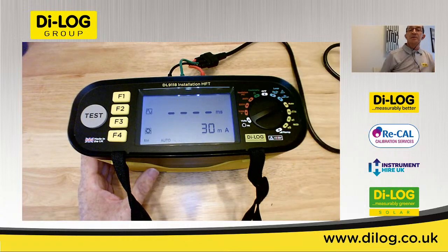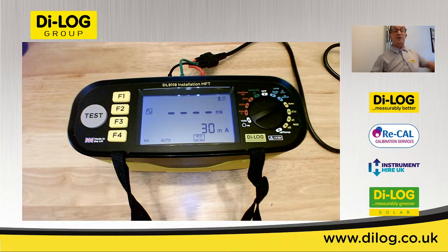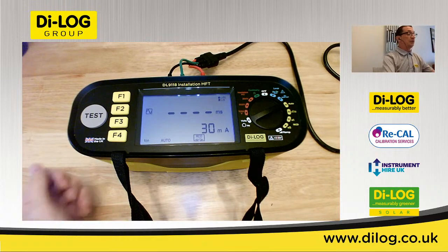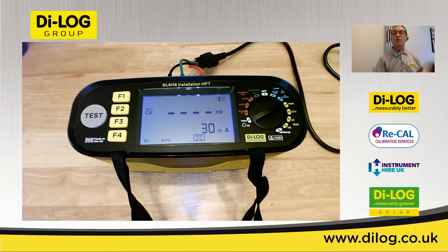We've also got the auto sequence, which is how probably most of you use this feature, especially if you're testing on your own. This makes it very simple for single person testing. So with the auto sequence, the tester is going to go through all of the tests, and all you're doing is resetting the trip at the board every time it breaks out.